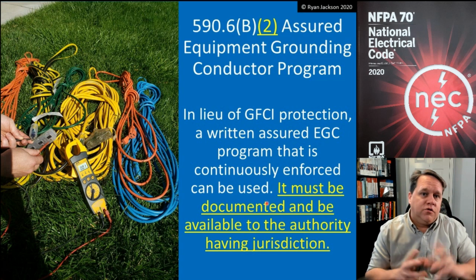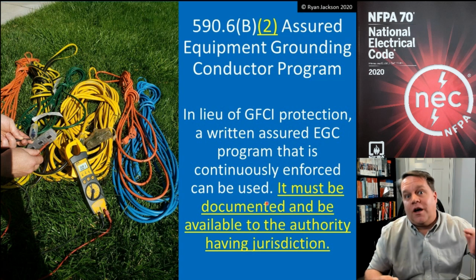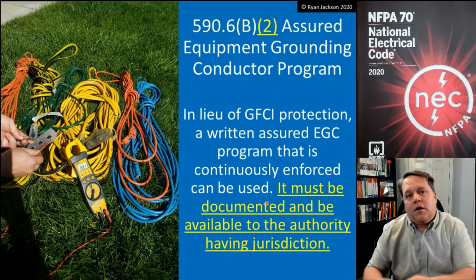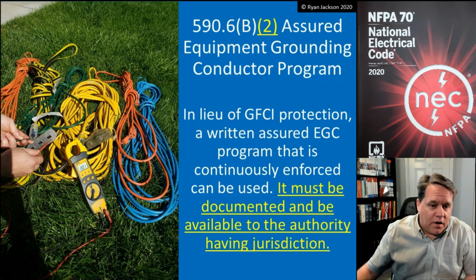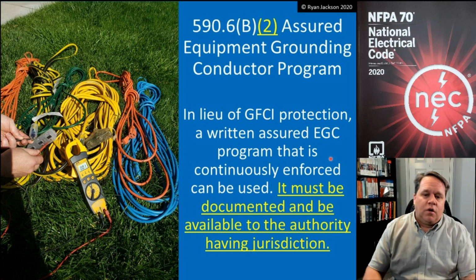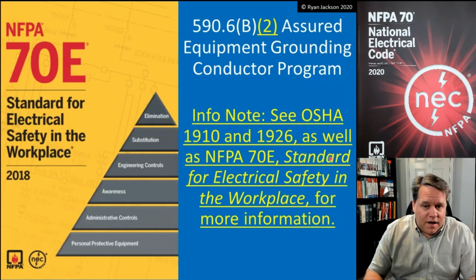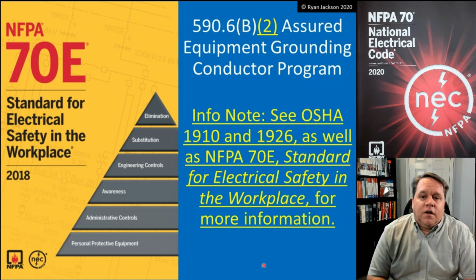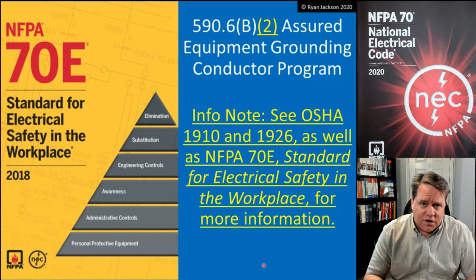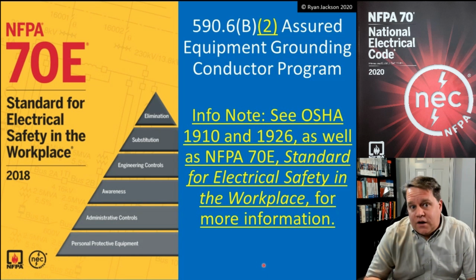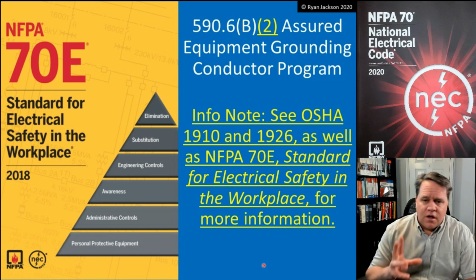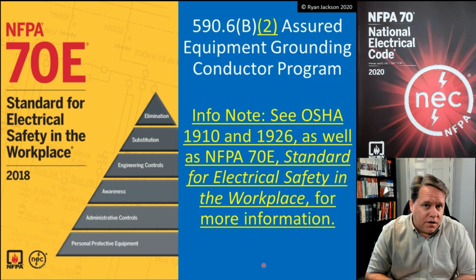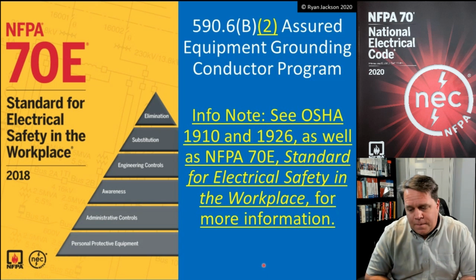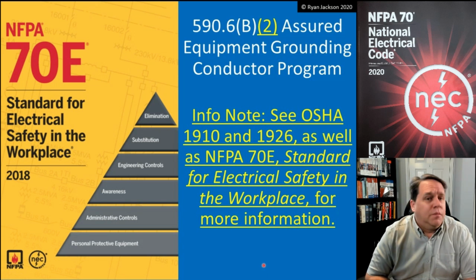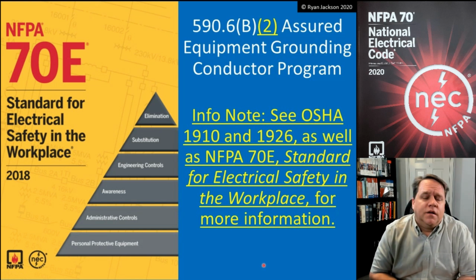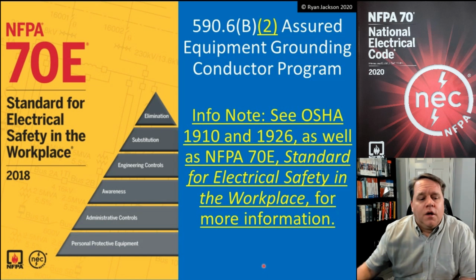So if I had a 240 volt cord that I was going to plug into a 250 volt receptacle and I didn't want to have GFCI protection, then I could perhaps utilize the Assured Equipment Grounding Conductor Program. Got to make sure it's continuously enforced, it's got to be documented, has to be made available to the AHJ, and then there is an informational note as well that says OSHA 1910 and 1926, as well as NFPA 70E, the standard for electrical safety in the workplace, all reference the Assured Equipment Grounding Conductor Program. But again, at the end of the day, I think we all know that GFCI protection is probably a better solution, but it is recognized to use the Assured Equipment Grounding Conductor Program as well.